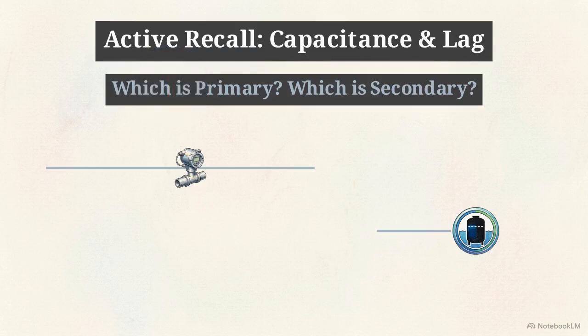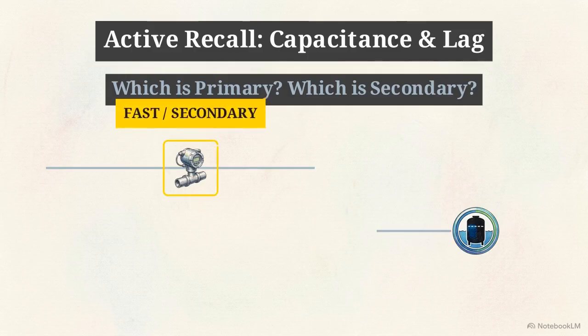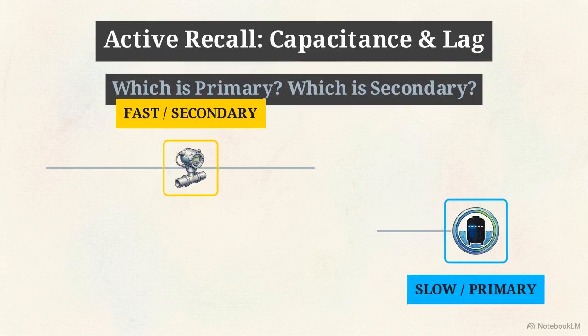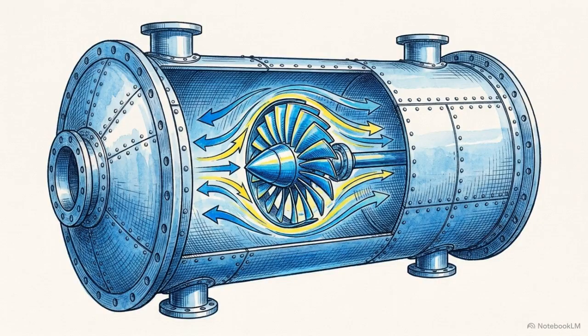The steam flow reacts to a valve change in seconds, making it our fast secondary PV. The column level is a massive liquid capacity that takes minutes to change. That makes it our slow primary PV. The rule of cascade design never changes. You always nest the fast, highly responsive variable inside the slow, high-capacity variable.